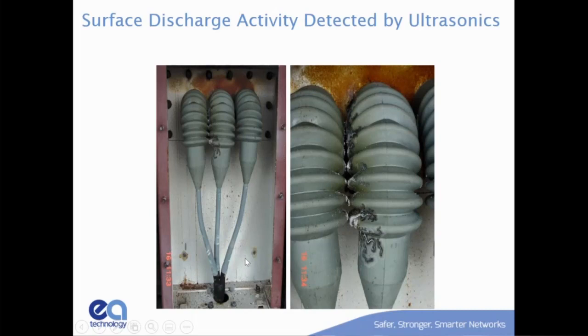I can also see that I've got a lot of rusting in that. When you have nitrous oxide inside that cabinet, there was no evidence of water. You can see the bottom is dry as a bone. But up here, where there was all this nitrous oxide, it was actually causing the steel to rust and the bolts to rust. Another good indication of PD.